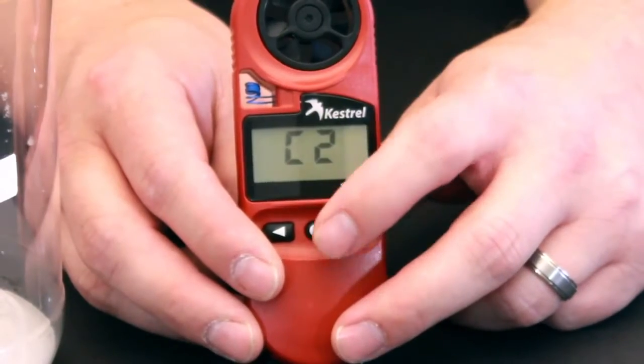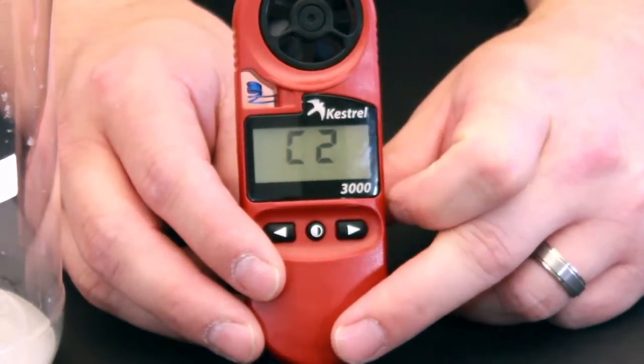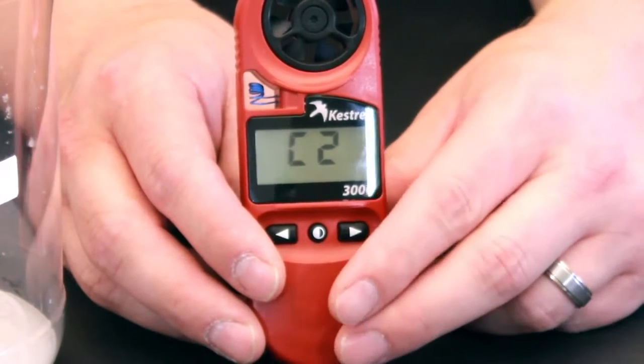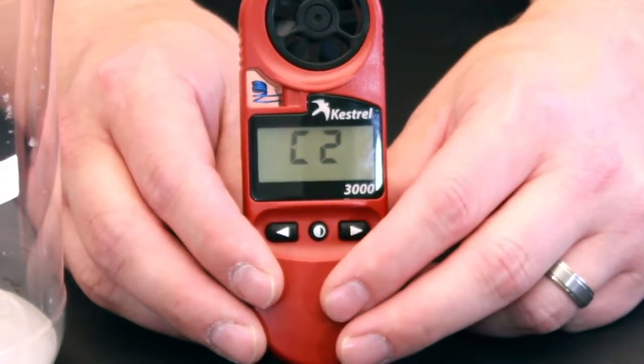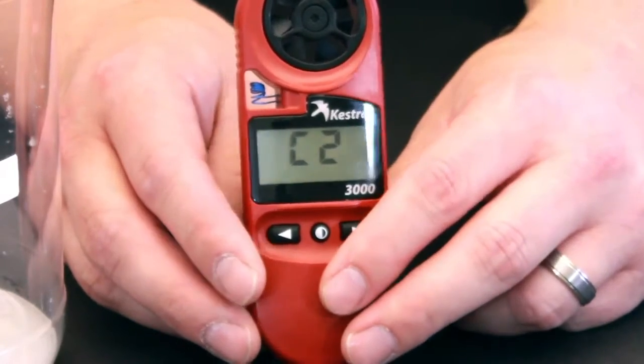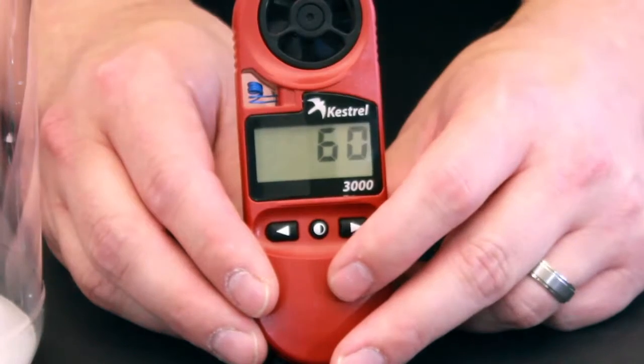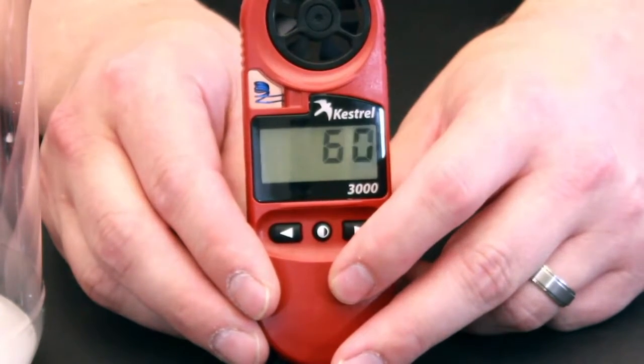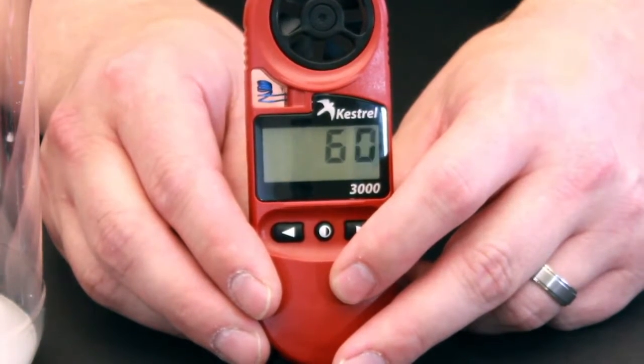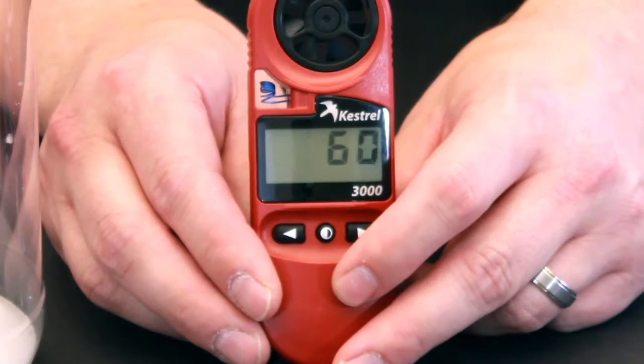We've wiped off the Kestrel and now we see that there's C2 on the screen. This means it's calibration of the second jar of sodium chloride. So when we're ready, we'll pull our sodium chloride jar out and hit the button, and you'll see it start counting down from C2 to 60. That means 60 minutes in the sodium chloride chamber.